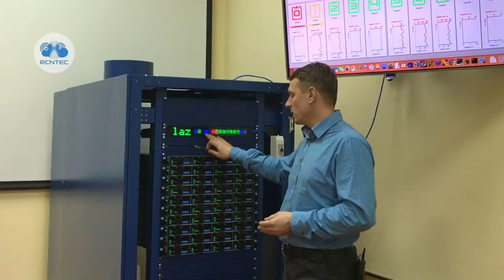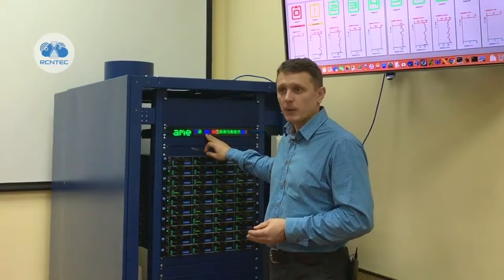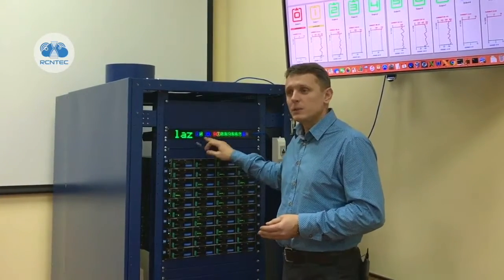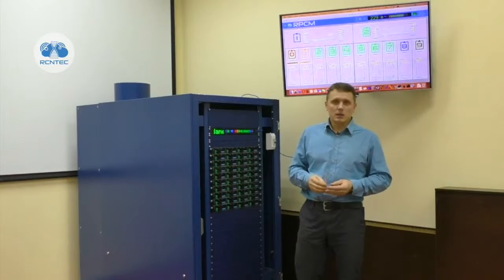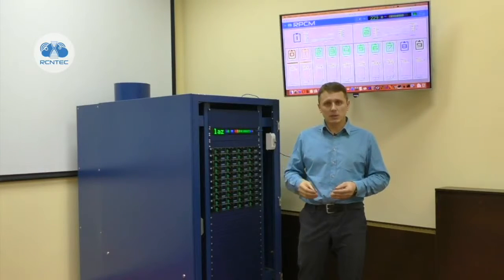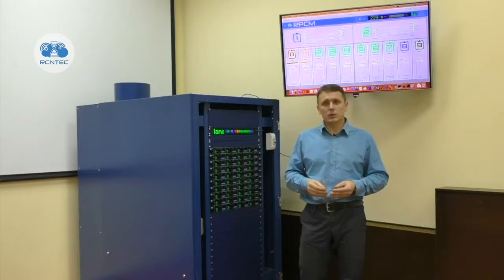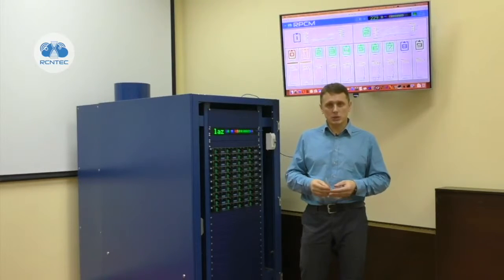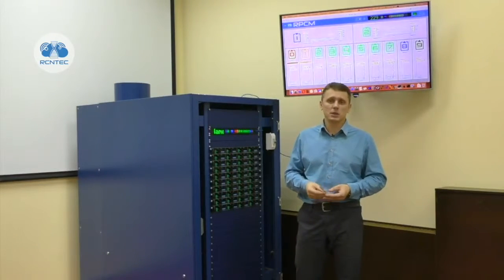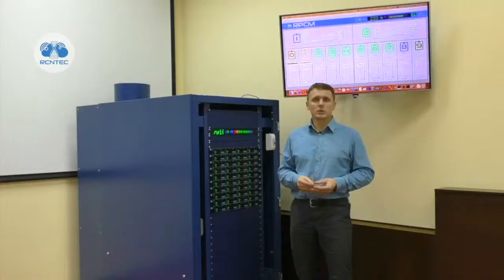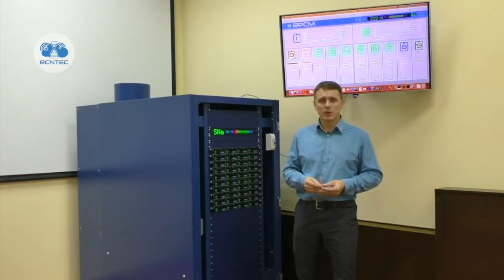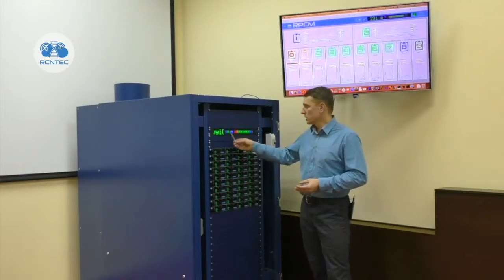In the event that both power inputs get turned off, there is a built-in battery within RPCM whose task is to provide energy for saving of information regarding the failure. It also allows for notifying external monitoring systems and administrators if the network is still capable of transmitting data. This RPCM model has a power consumption budget of 3840 volt-amps with 16 amps inlet current. 32 and 63 amps models are also available.